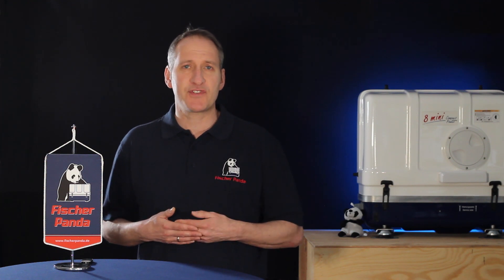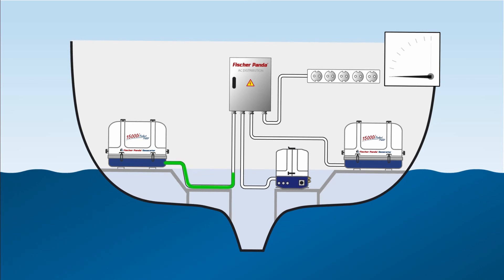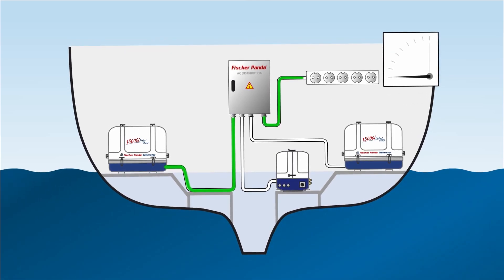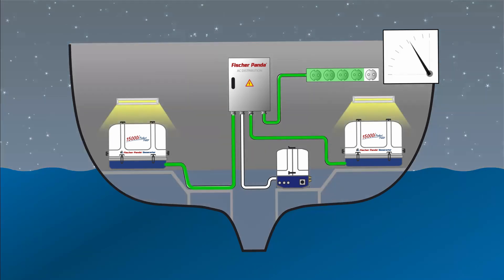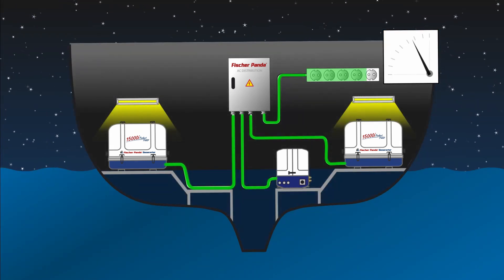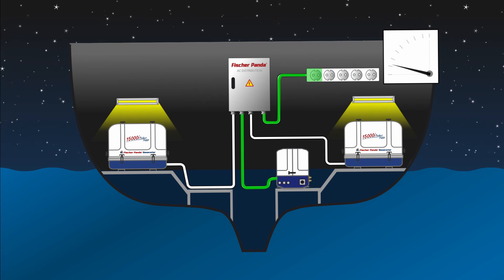On larger yachts you can expand the system using Fischer Panda I-Series generators — connecting three generators in parallel. A typical system could involve two similarly sized generators for main applications running during the day, and a smaller third generator used as a night generator, providing the lower power requirements usually needed during nighttime periods.